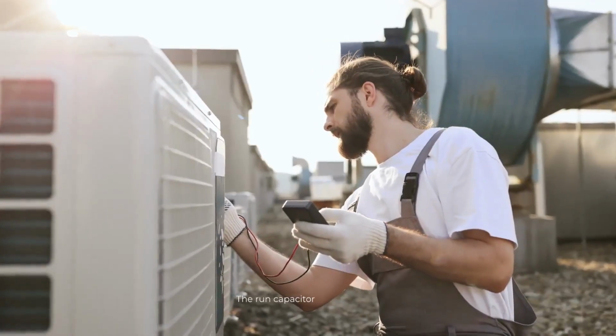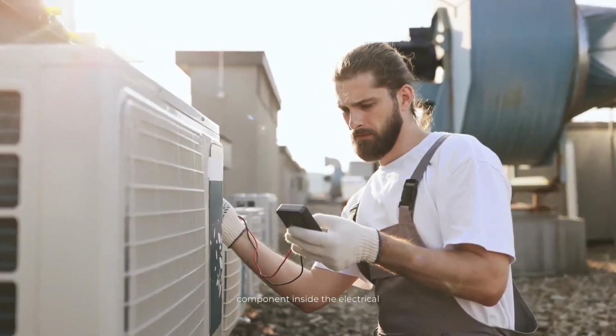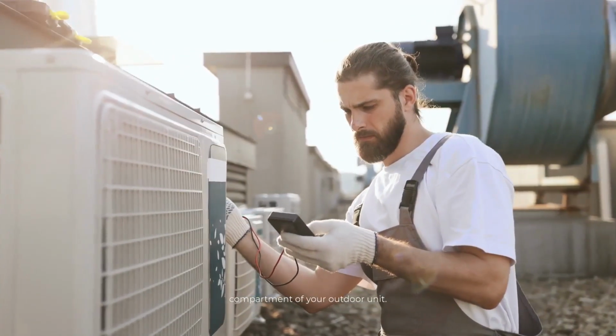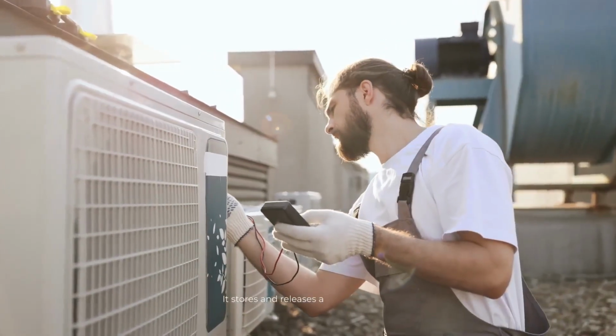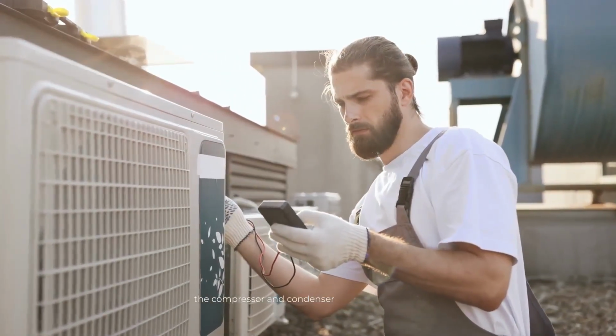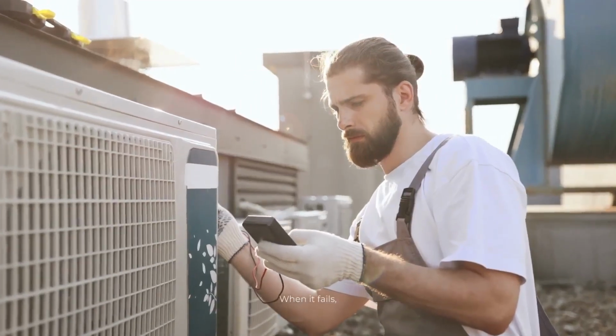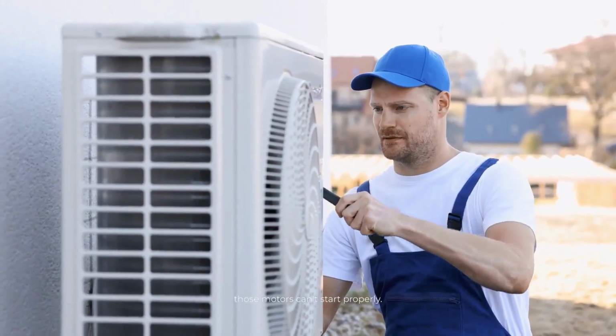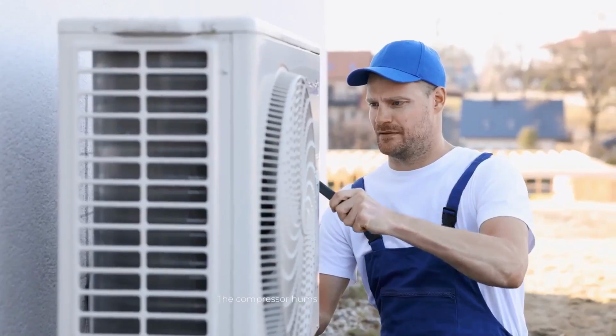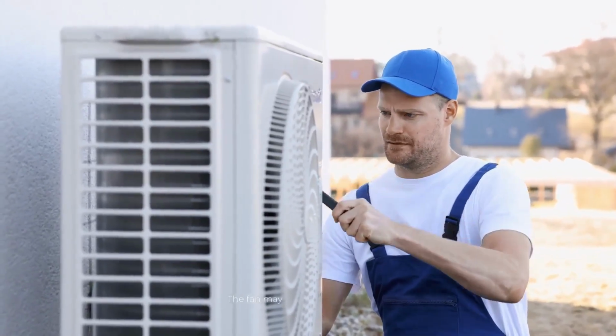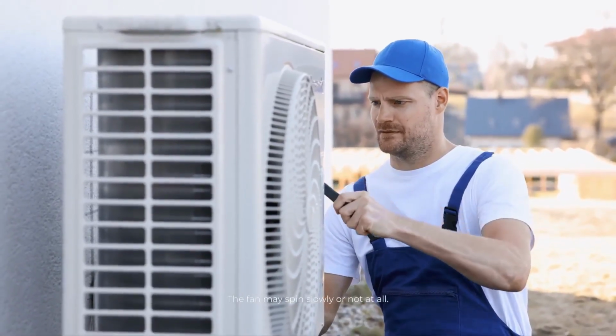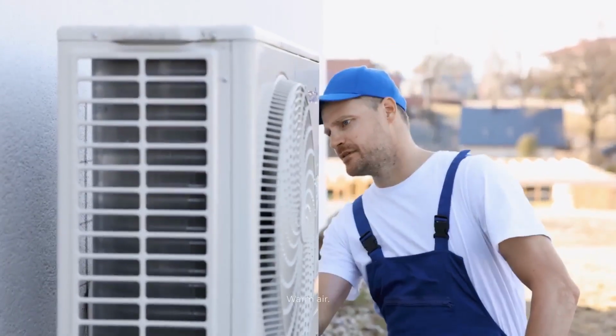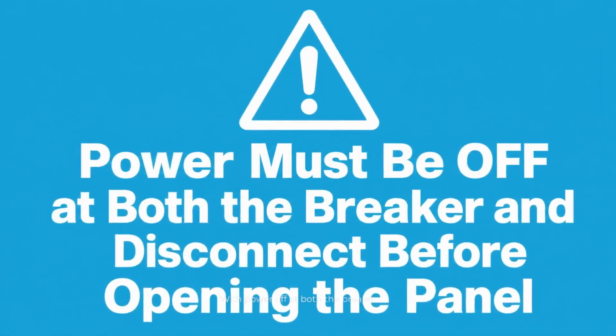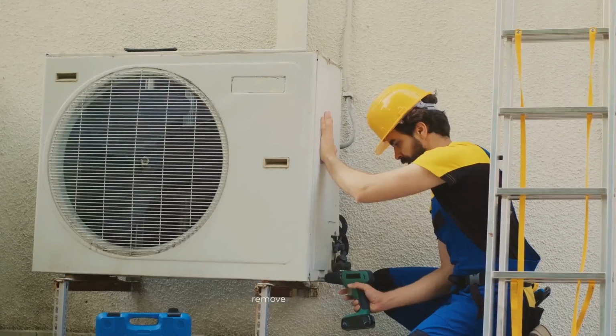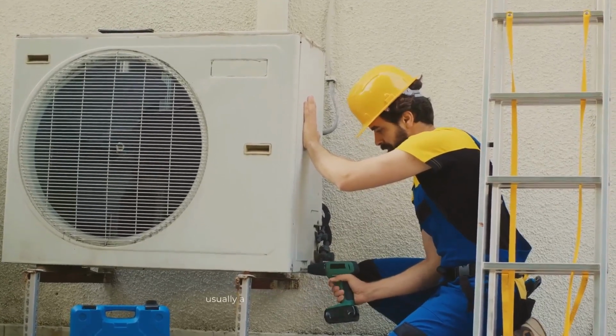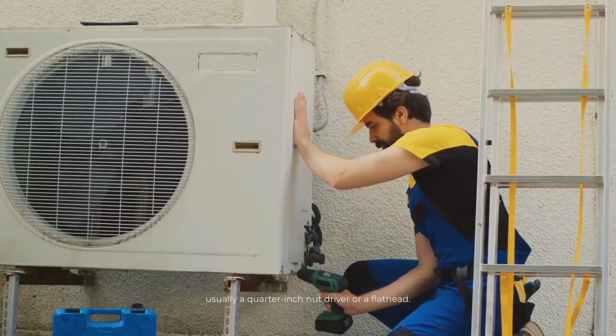The run capacitor is a cylindrical component inside the electrical compartment of your outdoor unit. It stores and releases a charge to keep the compressor and condenser fan motor running. When it fails, those motors can't start properly. The compressor hums but won't kick on. The fan may spin slowly or not at all. Result: warm air. With power off at both the breaker and the disconnect, remove the access panel, usually a 1/4-inch nut driver or a flathead.